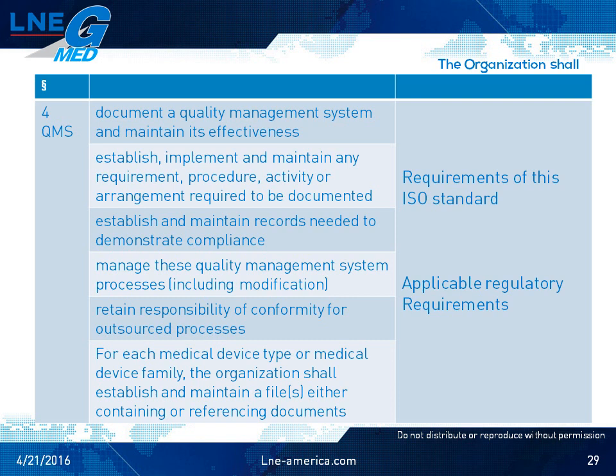If we look at the requirements directly linked to the QMS structure and implementation, conformity to applicable regulatory requirements has been added to conformity to the standard. Indeed, in most cases, the regulation imposes provisions to be fully integrated into the QMS. This is the case, for example, of the approval application phase or the post-market monitoring. The difficulty sometimes encountered is the integration of all the requirements of several regulations into one consistent and applicable quality management system.